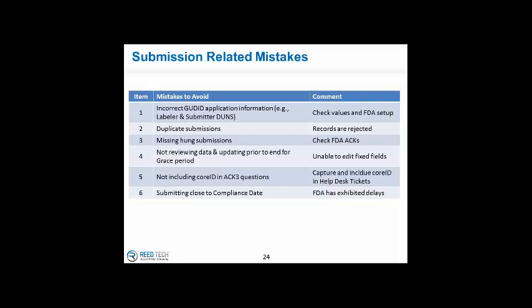Now, I will mention this, the FDA does allow the direct marking DI to be the same as what is referred to as the base product. So for labeling and direct marking, you can have the very same device identifier. As an option, you can have two different device identifiers. So a little bit confusing, but I would receive that scalpel, for example, in a box, and that box would have one DI. I open the box up, and oh, lo and behold, there's a different number etched into the scalpel itself. So that's all legitimate and recorded at the FDA.